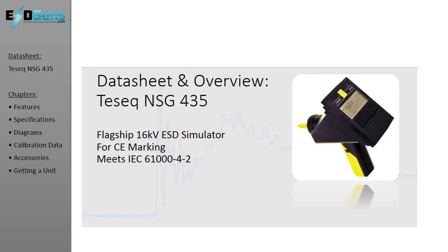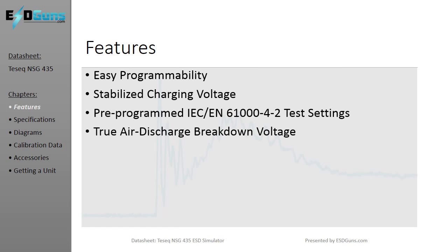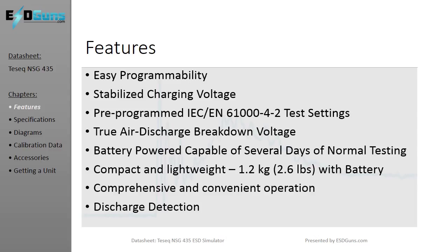Teseq NSG 435, one of the most effective and proven models on the market. Also one of the most popular rental units for short-term troubleshooting and pre-certification. The NSG435 produces reliable and consistent discharge waveforms ideal for electrostatic immunity testing, evaluation, and compliance. In addition to a user-friendly interface, quick access to test levels for IEC compliance standard 61000-4-2 makes the unit easy to use.